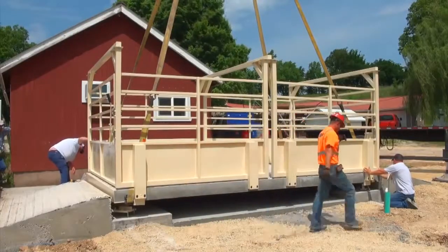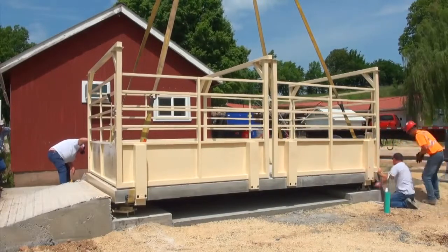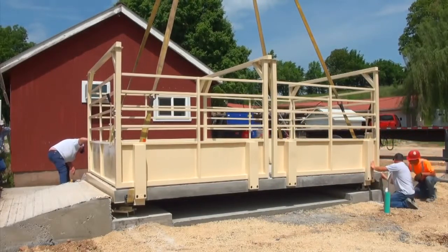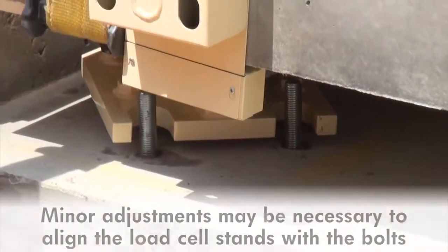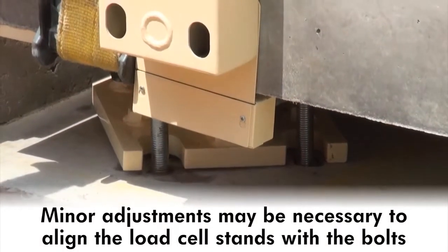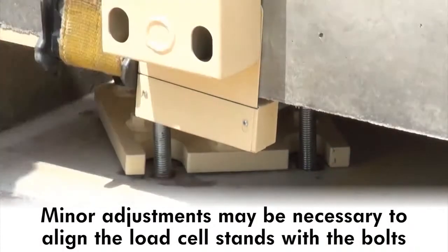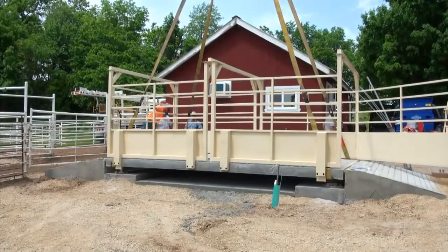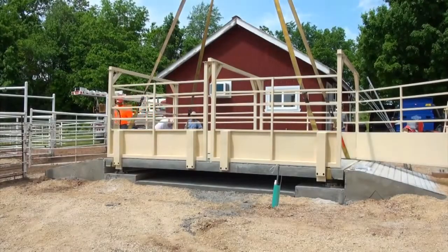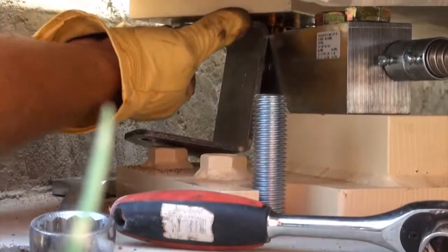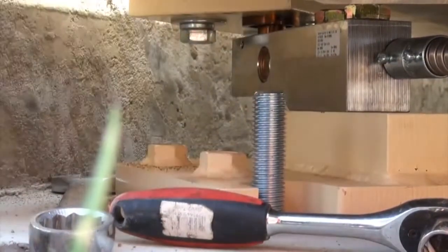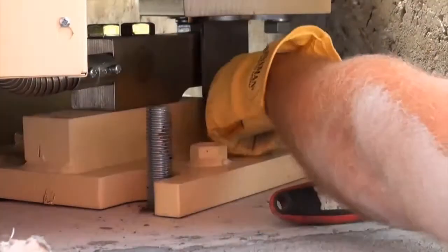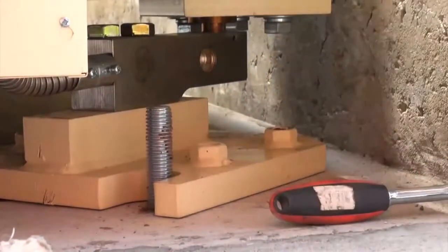Lower the weigh bridge carefully over the foundation, aligning the anchor bolts with the slots in the load cell stands. This may take some minor adjustments to get the load cell stands aligned with the bolts. Set the weigh bridge down completely onto the load cell stands. Next, remove all of the shipping brackets from each of the load cell stands. This will put all of the weight completely onto the load cell stands.